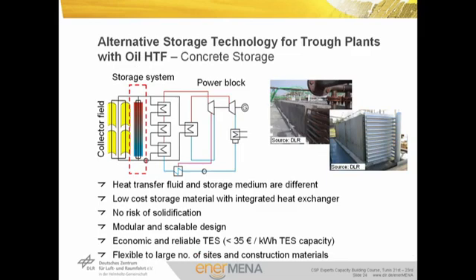An alternative approach to reduce the cost of storage material is to use solid storage media instead of molten salt. An attractive candidate material is concrete. For these systems, the heat transfer fluid is different from the storage medium. Low-cost storage materials are used in combination with an integrated heat exchanger. There is no risk of solidification. The design is modular and easily scalable. Analysis shows that an economic and reliable thermal energy storage system could be implemented at a cost of less than 35 EUR per kilowatt hour.